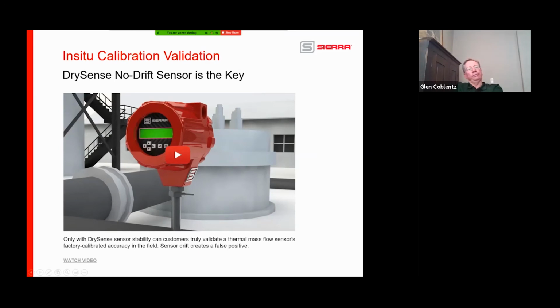Throughout the whole presentation here, we've talked about the DrySense, the no drift sensor, the lifetime warranty. And this video is also on our website. We're gonna watch this video as well. For one reason, I need to give my voice just a little break. But there's some powerful things in here because a lot of the competitors will call out ways to calibrate their meter in the field. Well, no one is calibrating a thermal mass flow meter in the field because you need a primary standard to do it. And you're not putting a primary standard in a customer's line to calibrate it, okay? So all of these things are validations in the field.